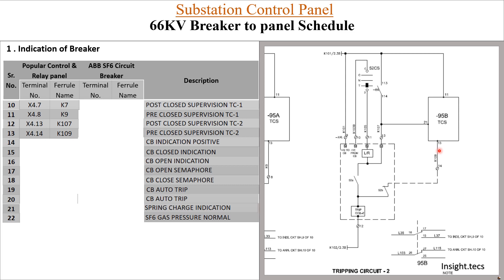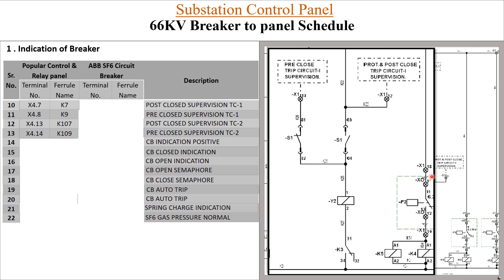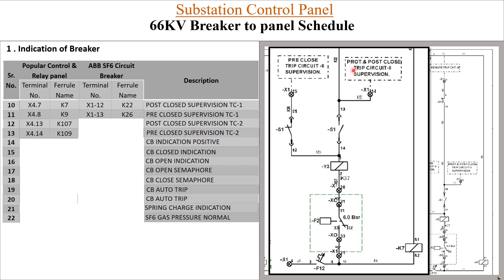Now looking at the breaker diagram, for trip circuit 1: post-close is at terminal X1-12 with ferro K22, and pre-close is at X1-13 with ferro K26. For trip coil 2: post-close is at X1-14 with ferro K32, and pre-close is at X1-15 with ferro K36. You can easily get all these details from the drawing.